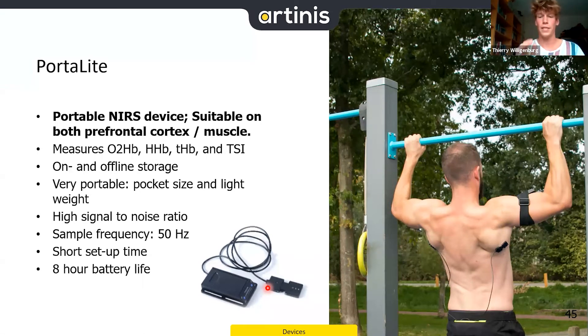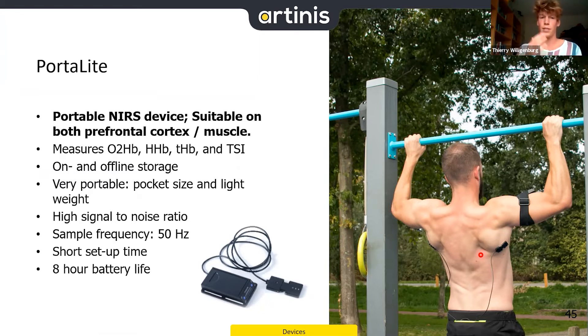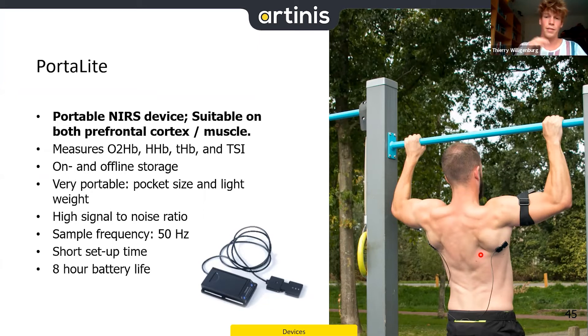The Portalite system is similar to the Portamon — also three transmitters firing to one receiver — but has a flexible probe, making it easier to measure rounder muscles. It can also measure the prefrontal cortex since it fits the slightly curved forehead area. It has a higher sample frequency of 50 Hz compared to the Portamon, though for typical oxy, deoxy, and TSI changes this higher frequency is not always necessary.